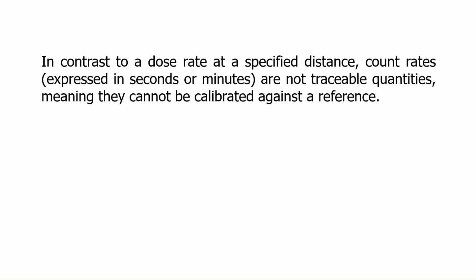In contrast to a dose rate at a specified distance, count rates, expressed in seconds or minutes, are not traceable quantities, meaning they cannot be calibrated against a reference.